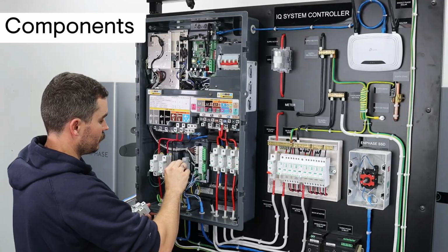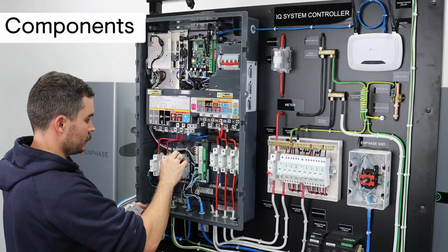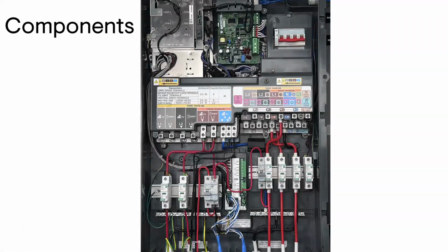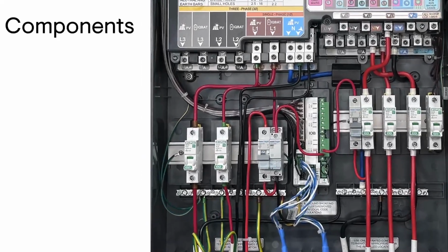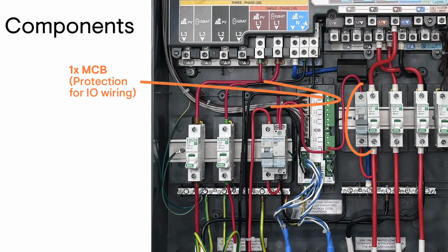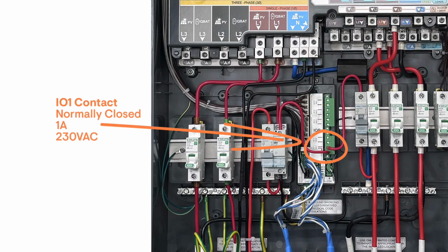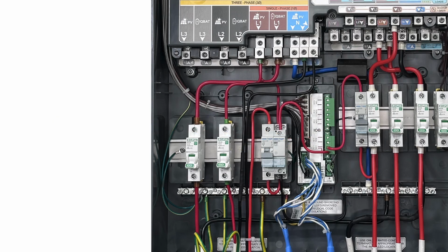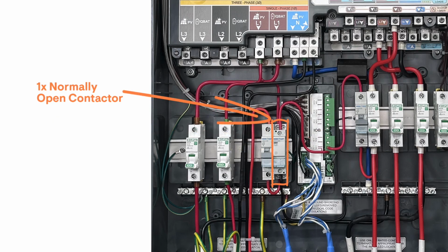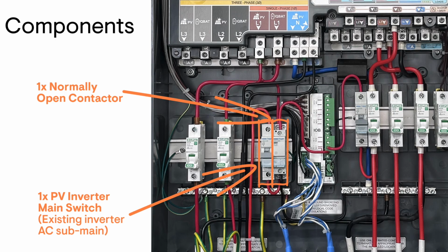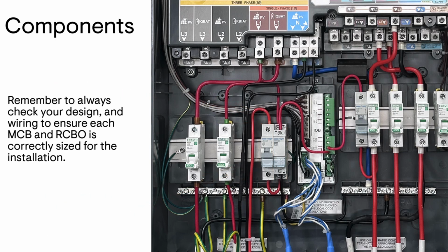To integrate a third-party string inverter with an IQ system controller, several additional components are required for the installation. The installation includes a miniature circuit breaker, protecting the wiring between backup supply and the I/O board. The I/O contact is rated at 1 amp and 230 volt AC. A normally open contactor and a PV inverter main switch are also required for the existing string inverter. The current ratings of these components should be selected according to the installation design requirements.